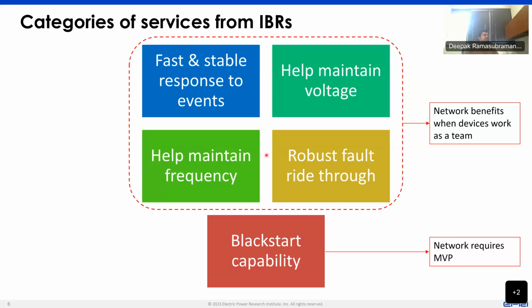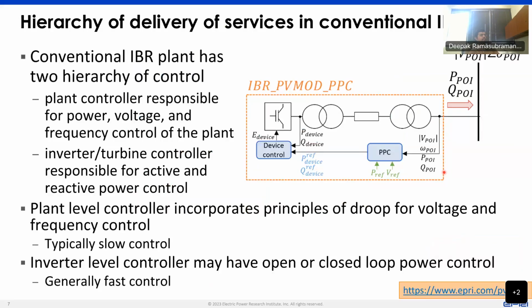So if we now talk about these four services that are possible from the inverter-based resource fleet, and we contrast it with how we had classified conventional IBR, future IBR and enhanced IBR, we now have to delve into some of the controls. So a conventional IBR plant has mainly two hierarchies of control. It has a plant controller that is responsible for power control, responsible for providing voltage response, responsible for providing frequency control, and so on at the plant level in a conventional IBR. And then there is a device level control, which is the inverter, which would usually follow the power commands provided by the power plant controller.